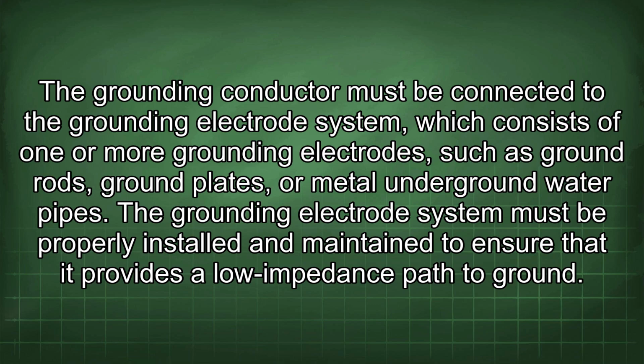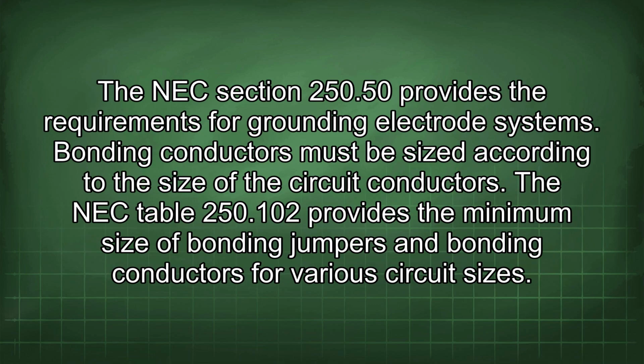The grounding electrode system must be properly installed and maintained to ensure that it provides a low impedance path to ground. NEC Section 250.50 provides the requirements for grounding electrode systems. Bonding conductors must be sized according to the size of the circuit conductors. The NEC Table 250.102 provides the minimum size of bonding jumpers and bonding conductors for various circuit sizes.